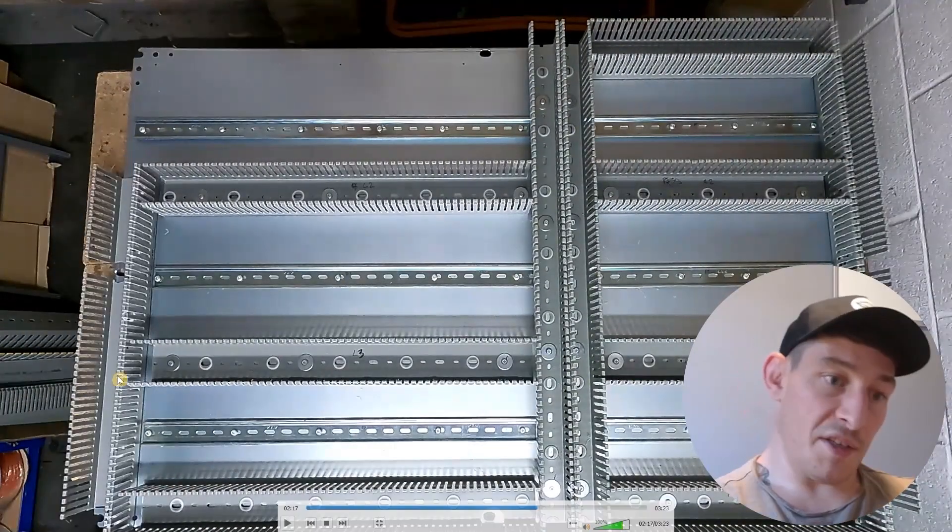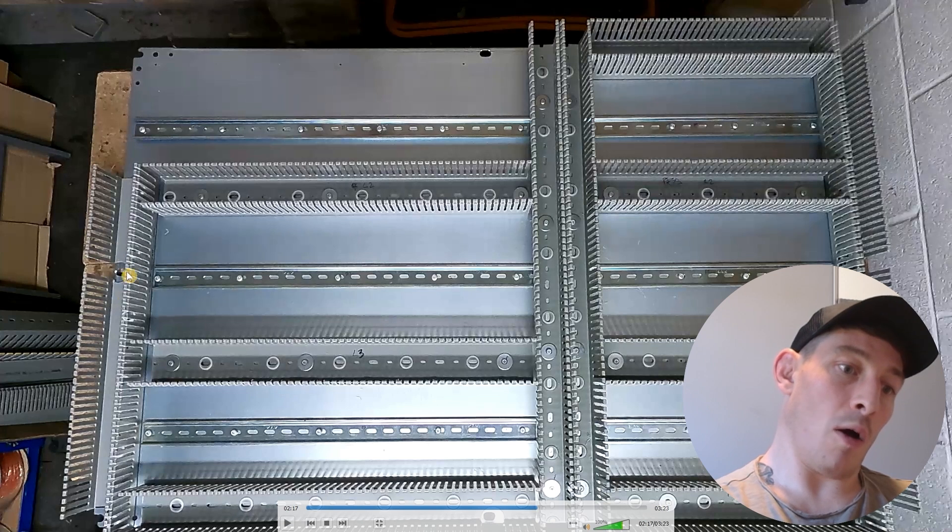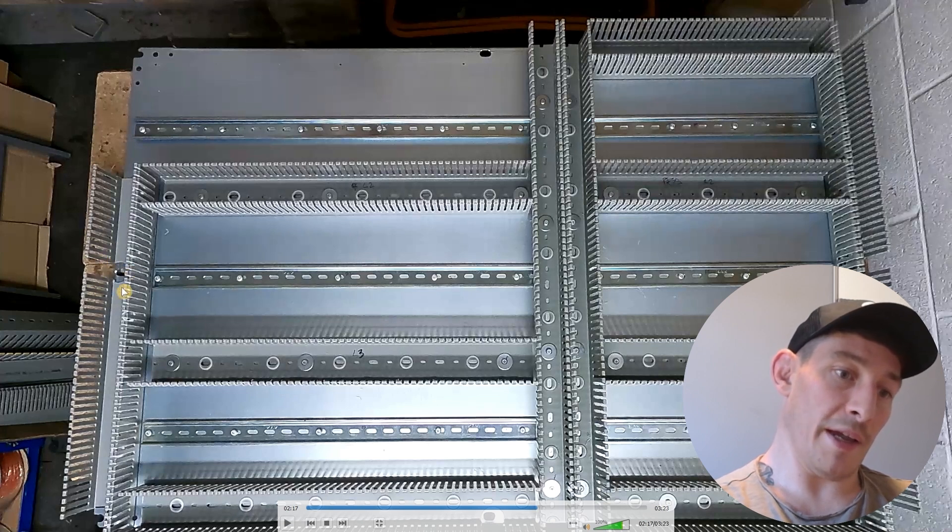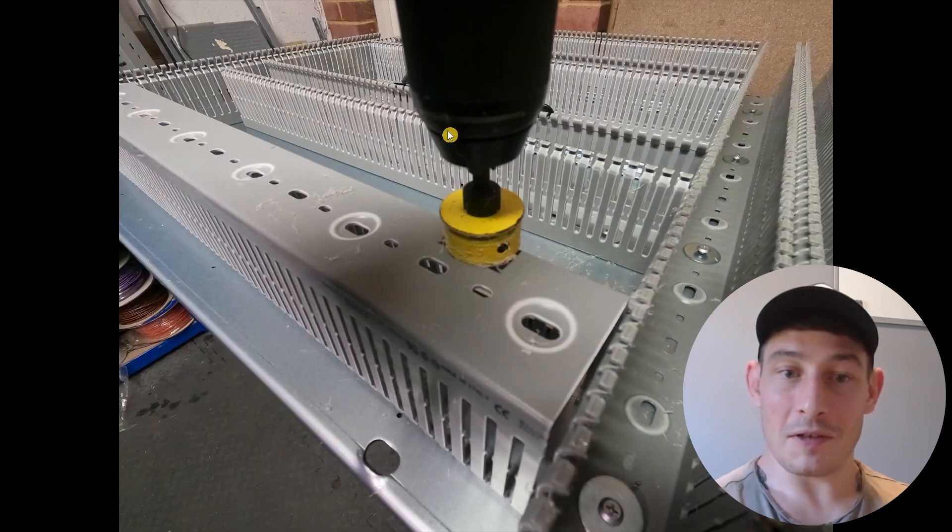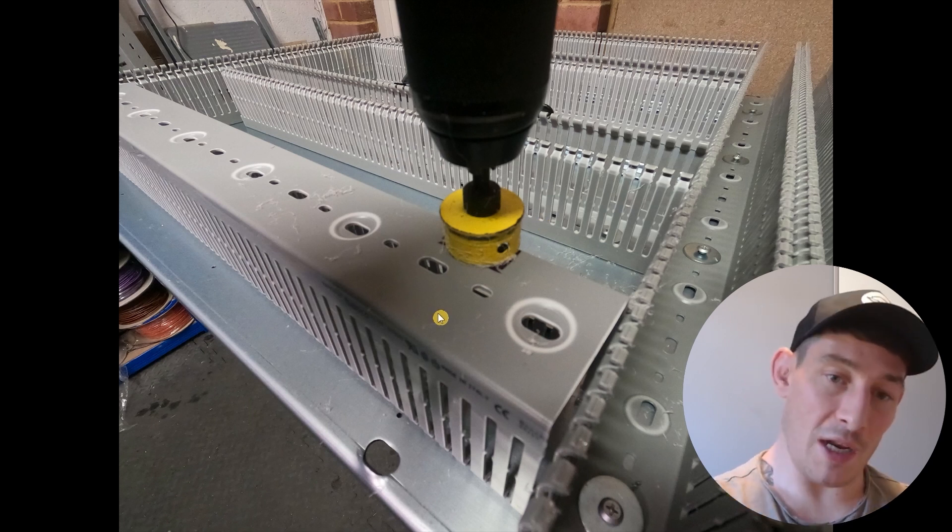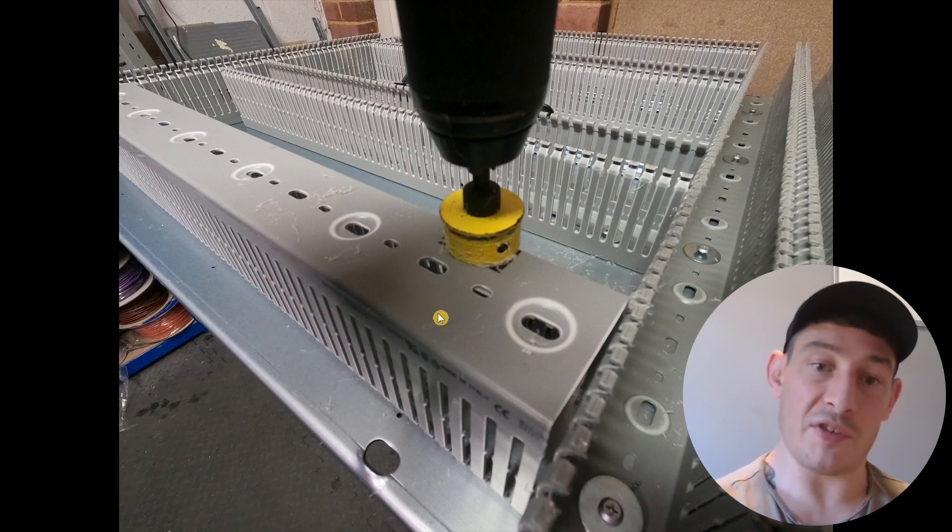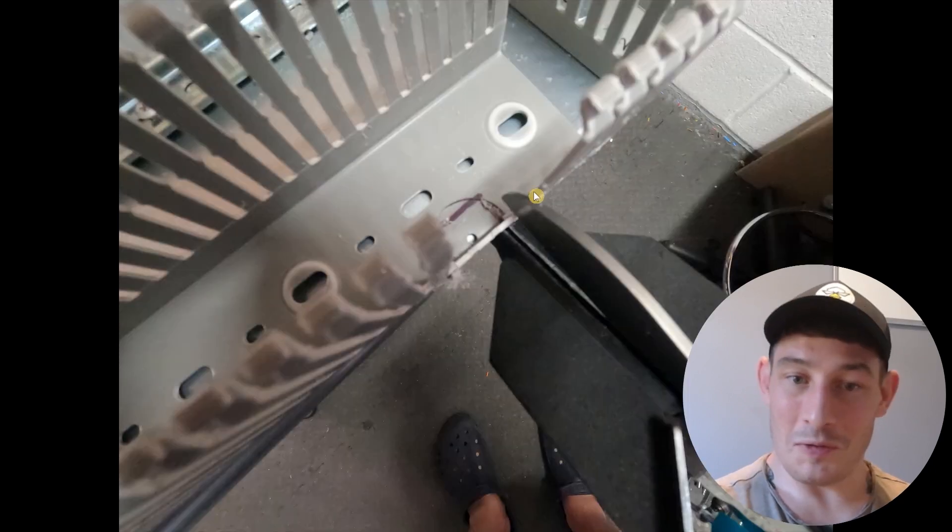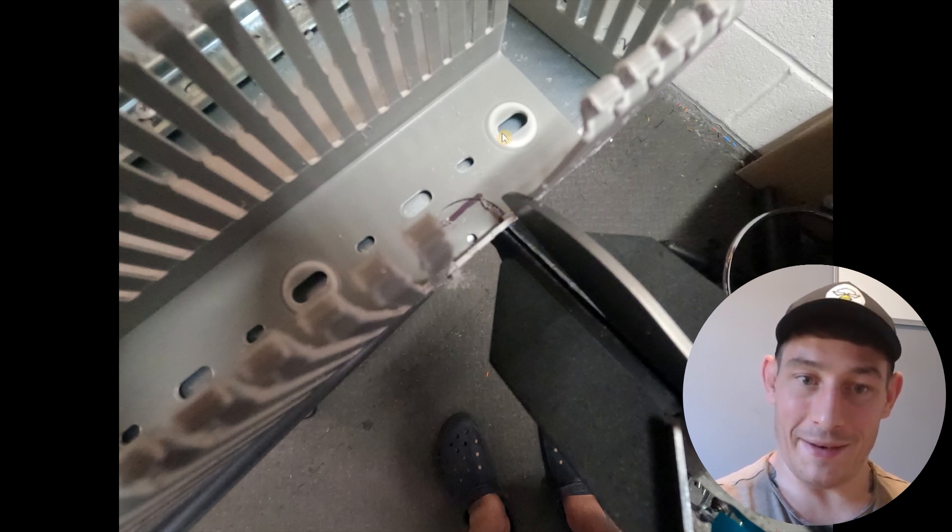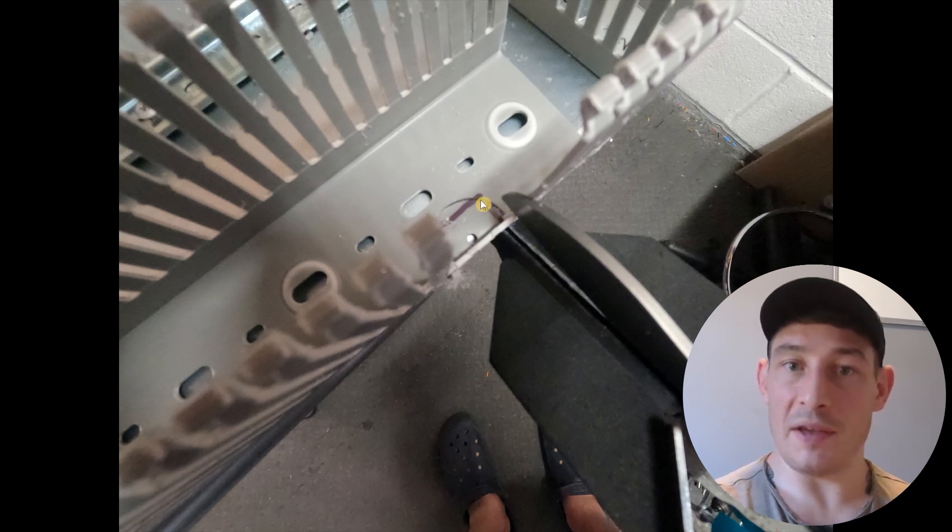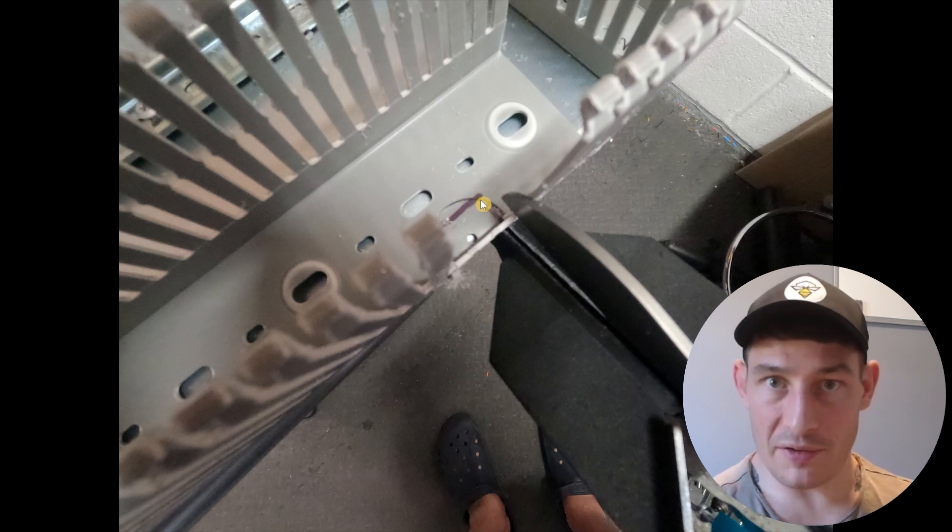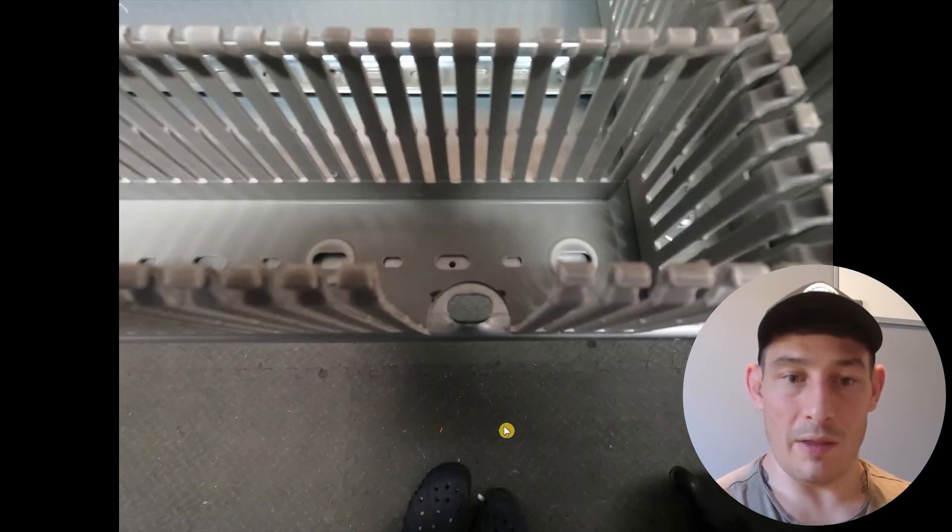So as you can see first piece of trunking I'll just cut out with a hole saw, this circular bit here over the fixing hole. So what that looks like, looks something like this. So obviously drilling on the underside something like that. Don't do it like this because I've done it like this before and it just ends up cracking bits of the trunking where it's so brittle. So a nice little cut out like that clearing that stud hole.